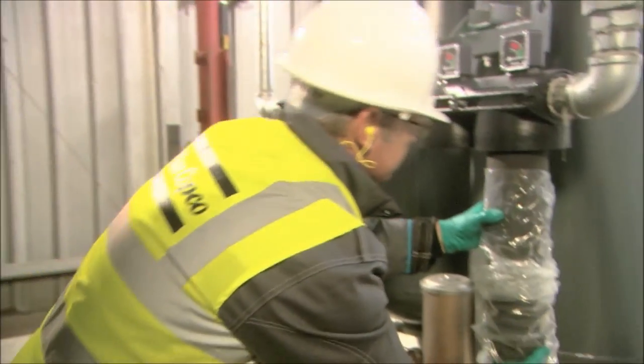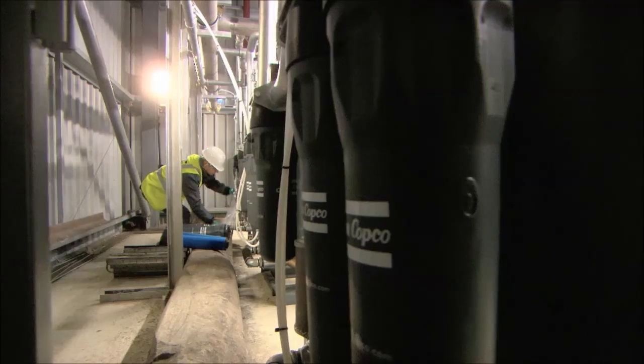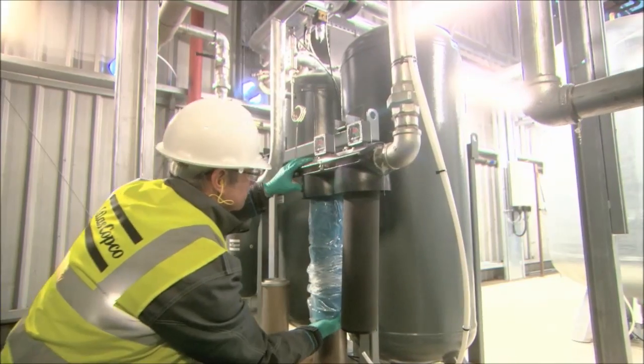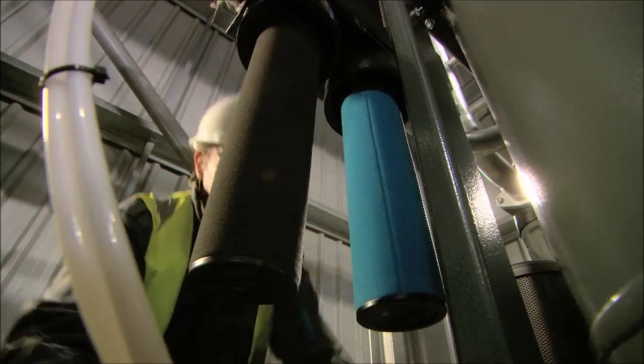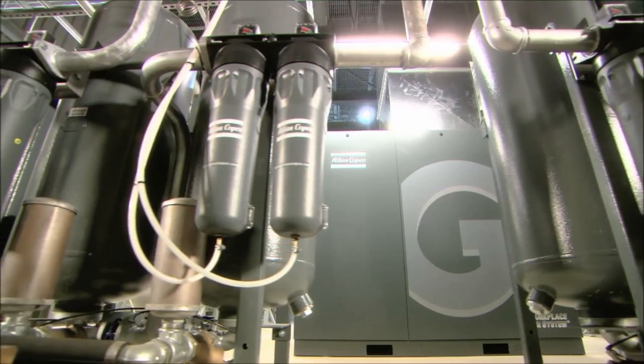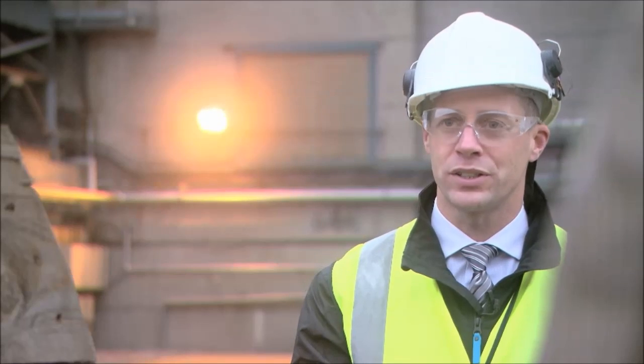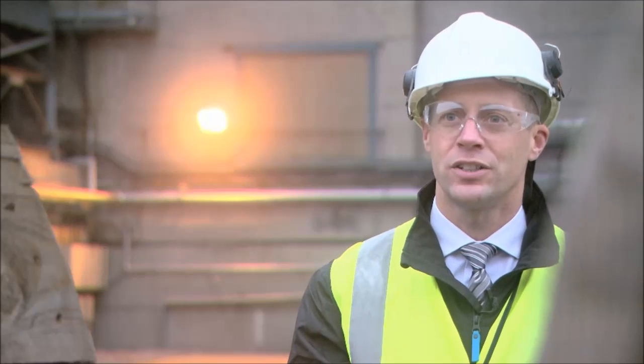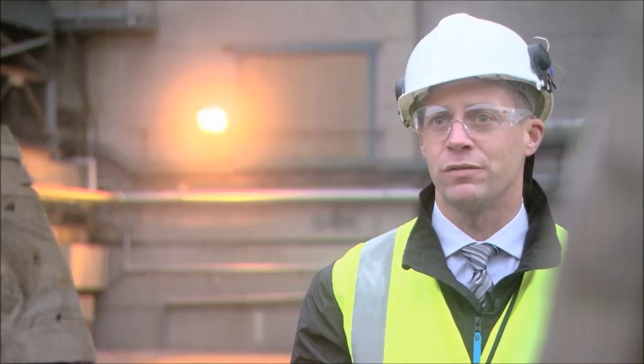FCC was one of the first companies to have Atlas Copco's brand new filter range installed. On the inlet side, we have an Atlas Copco DD Plus coalescing filter followed by a PD Plus coalescing filter. On the outlet stage, we have Atlas Copco DDP Plus particulate filtration. The advantage of these filters is that they offer typically half the pressure drop of conventional coalescing and particulate filters. This translates into an energy saving for our customer and ultimately a benefit for the environment.